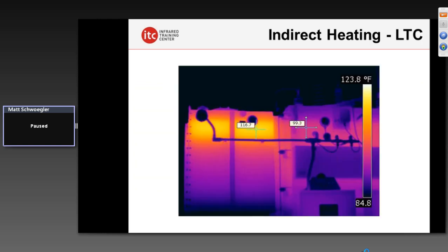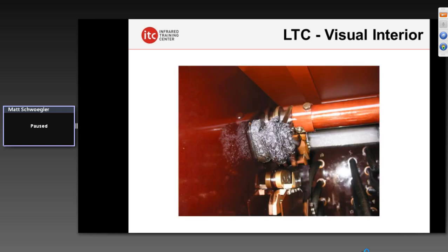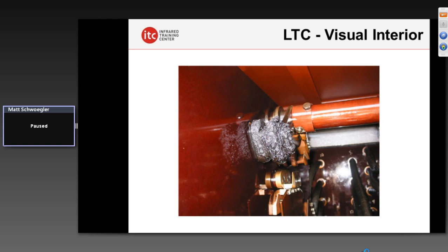Another example is a load tap changer coming off a transformer. Any type of heating on that load tap changer could indicate a very serious problem. In this case only about a 17-degree Fahrenheit temperature difference visible on the outside — and on the inside, it's game over. Copper melts at about 2,000 degrees, aluminum at about 1,200 degrees — it's just now a melted, charred mess. It was hundreds and hundreds of degrees warmer on the inside, not just a 17-degree Fahrenheit difference.